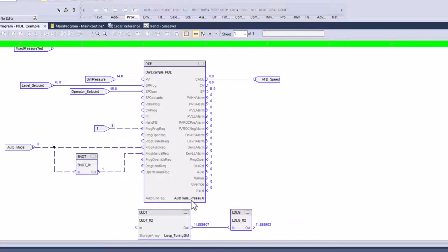Now, another thing I want to highlight is the auto-tune tag. From version 33 to version 36, Rockwell has a separate license you have to buy to be able to use the auto-tune. So if you're in that range, just know you have to reach out to Rockwell, buy the separate license, install it on your computer, and you're good to go. 32 and below, you do not. The auto tune is still part of the process, so don't worry about that. Moving forward on 37, I have talked to tech support, and they said they are completely getting rid of the auto tune altogether, but they do have an alternative software that already works really well with integrating with Rockwell, but I won't get too far into that, because that's looking into the future.